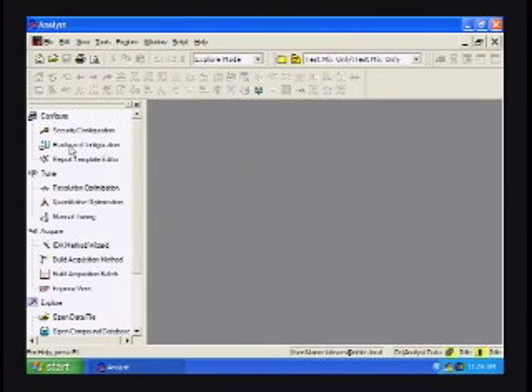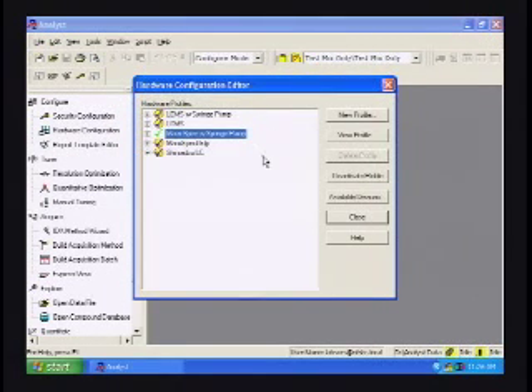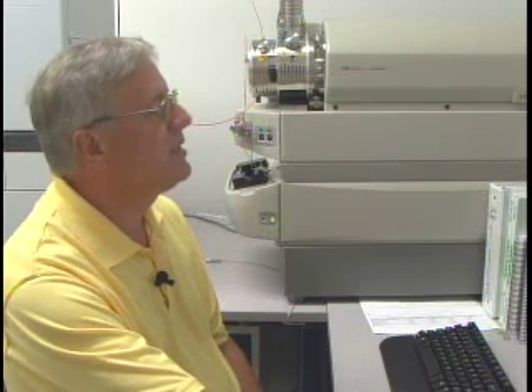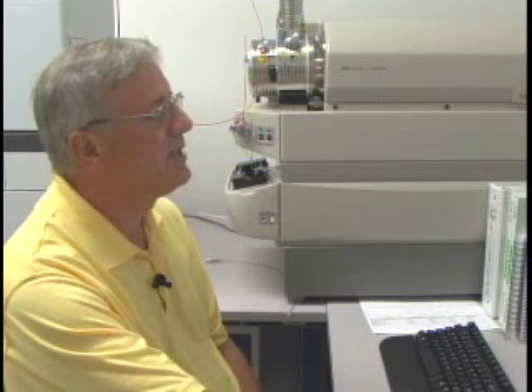Okay, in this particular segment we're going to cover tuning the instrument and checking the tune of the instrument. So the main thing we wish to do at this point is to make sure that the system is configured in the manner that we need. And it is. If it were configured with the LCMS spec, we would want to change the configuration to the mass spec with the syringe pump. The syringe pump is used to introduce the PPG or polypropylene glycol solution, which is the tuning solution, into the instrument. And as we can see, that is the selected profile at the moment.